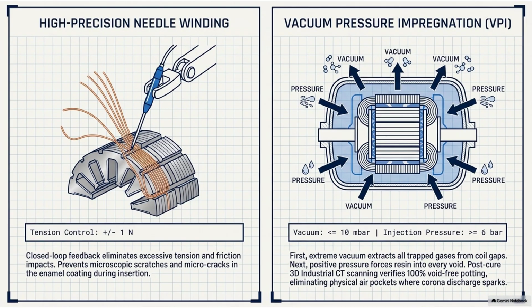How do you physically design a wire to withstand an electron avalanche? Well, you have to alter the chemistry of the enamel coating at the nanometer scale. Standard polymer resins eventually succumb to ozone and electron bombardment. So material scientists dope the enamel with inorganic nano-oxide fillers. Nano-oxide fillers? Right, these are typically microscopic ceramic-like particles like silica or alumina dispersed evenly throughout the polymer matrix. So when the partial discharge storm starts, the polymer chains might take some damage, but the electrons quickly hit these inorganic ceramic shields. And ceramic doesn't oxidize or degrade under electrical stress the way plastic does. It acts as a physical barricade. Precisely. It drastically increases the material's endurance.